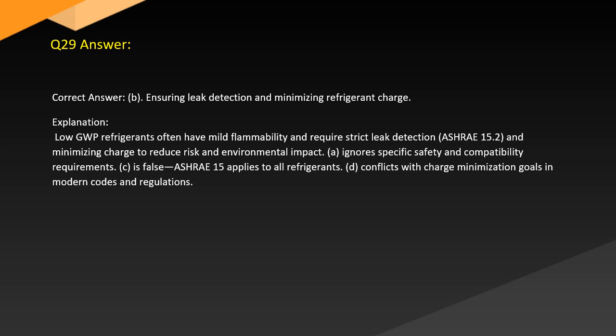Answer. Correct answer. B. Ensuring leak detection and minimizing refrigerant charge. Explanation: these refrigerants often have mild flammability and require strict leak detection per ASHRAE 15, and minimizing charge to reduce risk and environmental impact. A. Ignores specific safety and compatibility requirements. C. Is false. ASHRAE 15 applies to all refrigerants. D. Conflicts with charge minimization goals in modern codes and regulations.